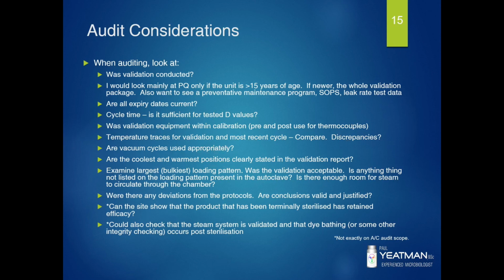So, for example, if you're sterilising media, do you have a fast or slow exhaust? You don't want a fast exhaust on, say, a liquid sterilisation cycle, because you're going to wind up with nothing left in your containers. Things like that. You might also want to use vacuum when steam penetration might be difficult, such as long piping or wrapped items.